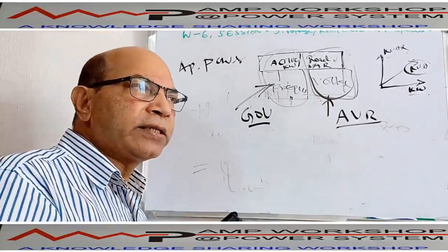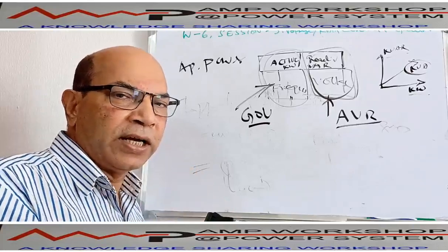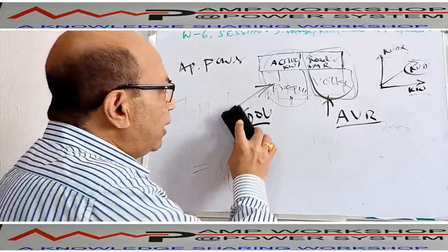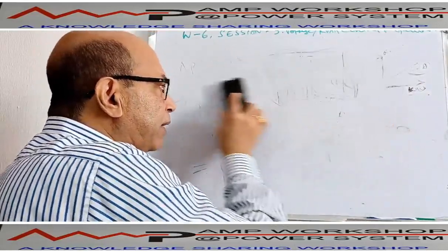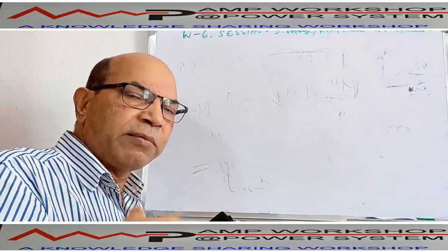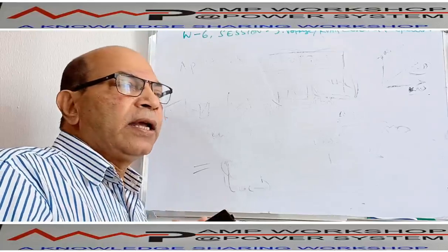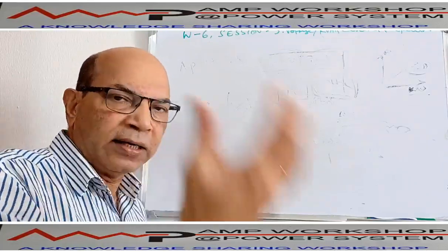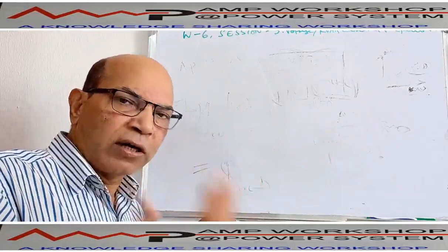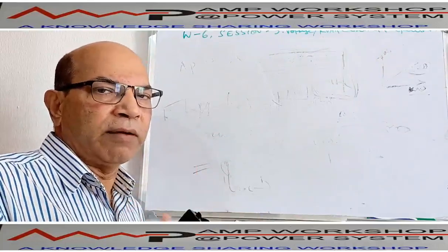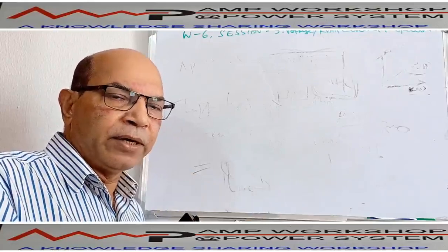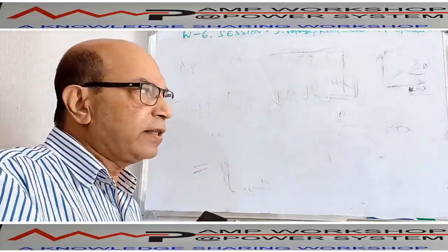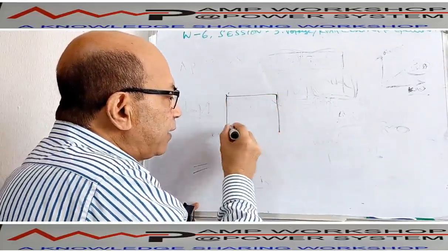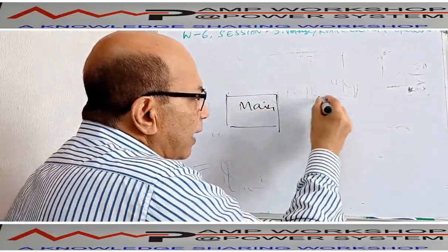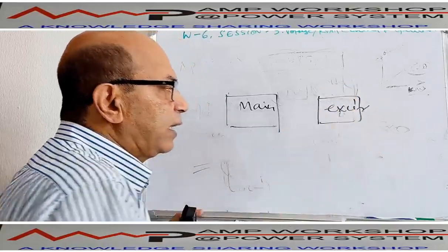Now we said that the rotor winding is getting excitation, but we do not give excitation to the rotor winding directly. If you see the actual generator, it has two generators in cascade, not only one. One generator we call the main generator, which is producing the main power, and the main generator has an exciter, meaning the rotor field. That rotor winding is getting DC current or DC excitation from another, small generator, which is also an alternating generator. It also has a stator winding and a rotor winding, but we call them the armature winding and the field winding. So in the case of the main machine, there are two generators: one is a big generator, the main generator, and the other is a small generator we call the exciter, which produces the exciting current and gives it to the rotor.